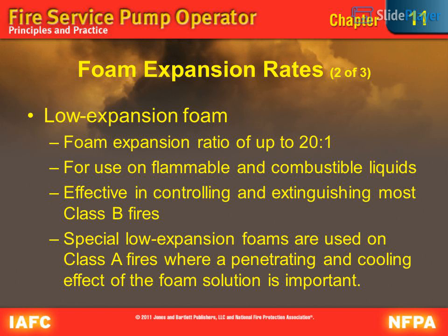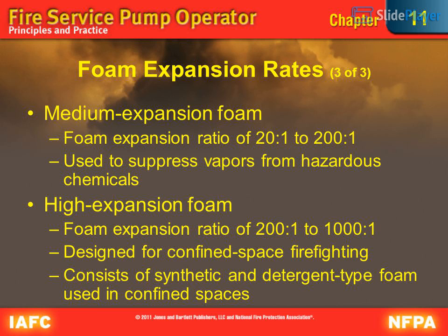Foam expansion rates, 2 of 3. Low expansion foam. Foam expansion ratio of up to 20:1. For use on flammable and combustible liquids. Effective in controlling and extinguishing most Class B fires. Special low expansion foams are used on Class A fires where a penetrating and cooling effect of the foam solution is important.